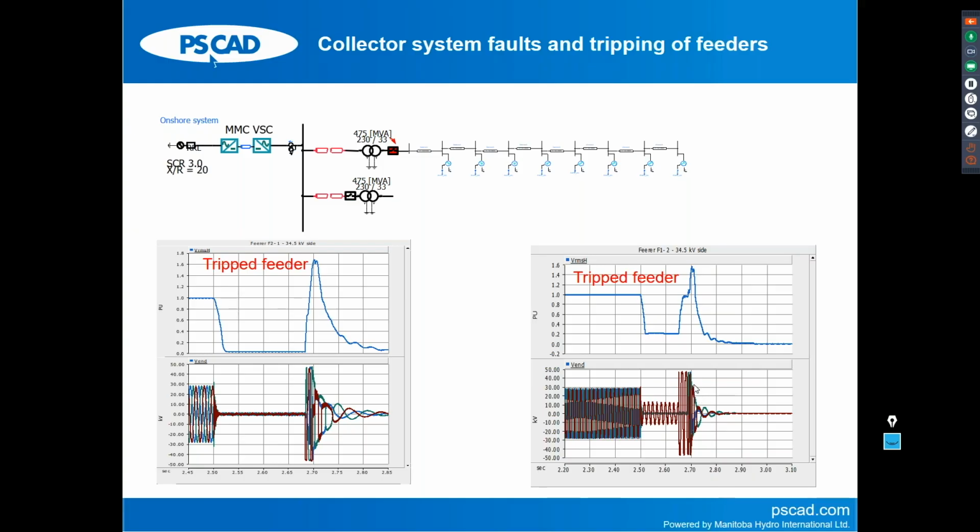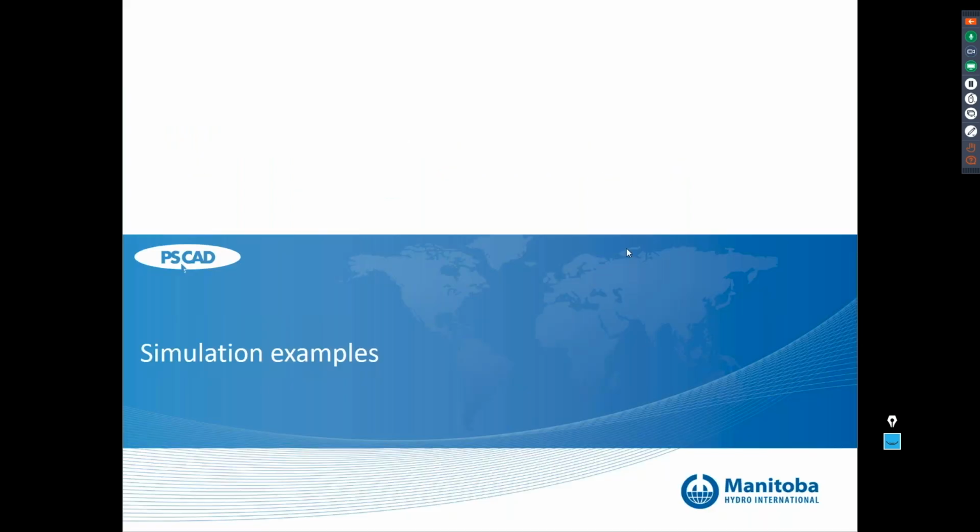So after the study, we have to go to the vendor and have a discussion, if you realize that this voltage is too much and it lasts for too long compared to your equipment's voltage withstand capacity. So that's again a very specific simulation.